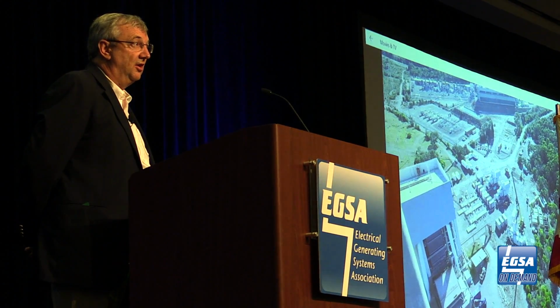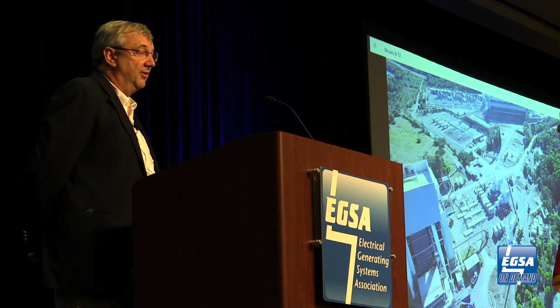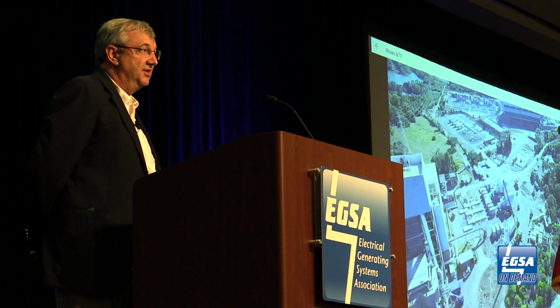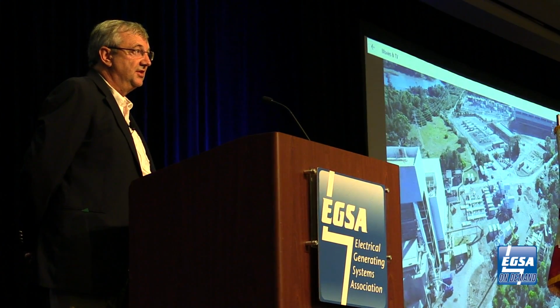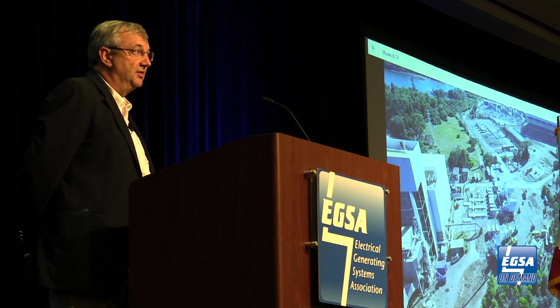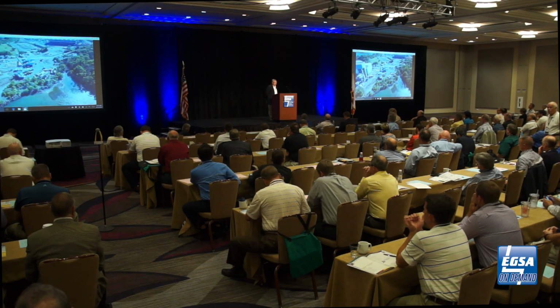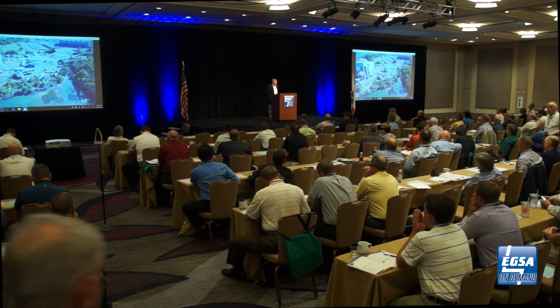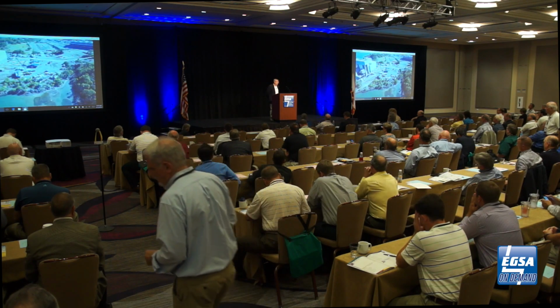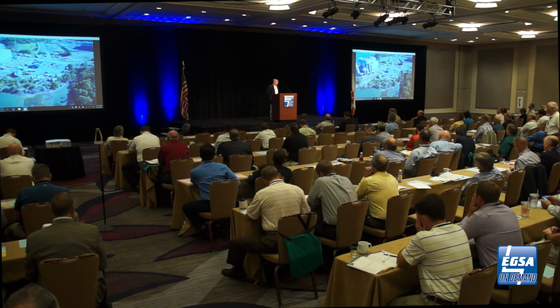Same thing applies when we're looking at grid voltage. If the grid voltage is too low, we turn on what we call our voltage support mode on the turbines or on the recips, and we add VARs into the system and bring the voltage back up to where it needs to be. Depending on the countries we're operating in, an example would be Argentina. Grid codes there require us to be able to do voltage support. If we're not, we're penalized financially in our monthly invoicing. They're not looking for frequency support, they're looking for voltage support because we're out at the end of the grid.